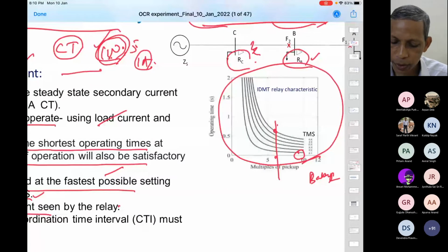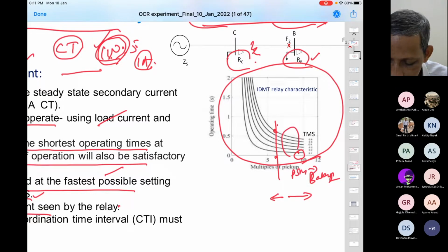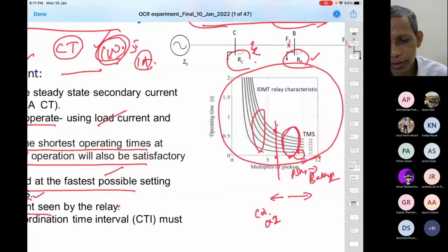Now see what happens here. What is the maximum fault current? What is the minimum fault current? When the fault current is at maximum, we are going to the right, and at minimum fault current, we are going to the left, on the axis of fault current divided by the pickup current, the PSM. In this portion, the time difference between any two curves is smaller compared to the time difference here on the left. Because we have to maintain a coordination time of 0.2 or 0.3 seconds, the coordination time will be ensured if you consider the right-hand portion, the maximum current level, not the minimum fault current level.